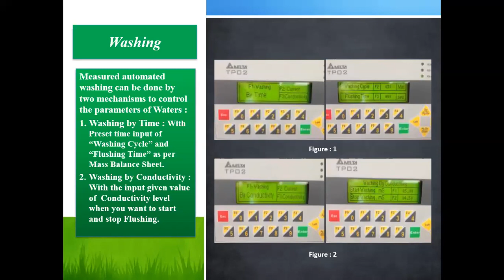I'll try to be a bit louder because somebody mentioned the audio is a bit low. The second option is washing by conductivity, where we can set the input value to whatever conductivity value we want, or TDS in easy terms, like 2,500 or 2,000 ppm. Once it increases by that value, the system automatically blows down that amount of water.